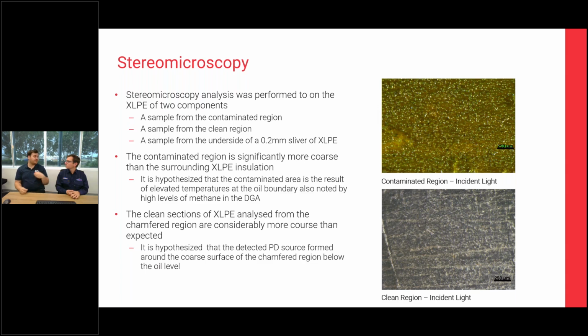It was interesting to see this type of data because it was polar opposite to what we were thinking before we broke it down, but it did line up with a lot of our data, because the higher pulse rate can also be somewhat explained by the fact it was multiple discharge sites. It wasn't one point discharging a set amount, it was multiple points discharging all over a select region, which is quite interesting once you start to correlate it backwards. Absolutely. And that typical discharge into oil will form the wart-like texture of the contaminated region, as implied in the photo. So everything aligned with that distributed partial discharge source at the chamfered region, due to the coarse nature of the XLPE preparation.